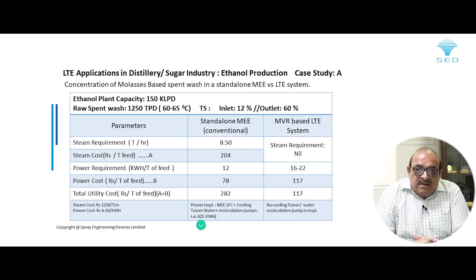In this particular application you will find there is no cooling water, no steam, and at the end we are having a steam saving of 1.36 kg per liter of ethanol, equivalent to 8.5 tons, which we are feeding to the multiple effect evaporator. Raw water saving will be 1.77 kl per kl of ethanol, about 265 cubic meter a day, along with OPEX savings of 6.18 Cr.